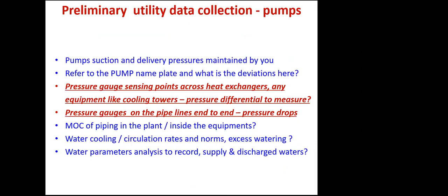I'm just giving a macro view of an industry trying to get ready for the energy audit. Each and every piece of equipment, right from the transformer, the motors, the production machines, the compressors, then the pumps. What are the pump suction and delivery pressures? The pump nameplate gives a lot of inputs. You store the nameplate or take its details and go with the pump manufacturer's OEM technical specifications. The nameplate gives the basic inputs, but the technical specifications tell you the operating temperature of the fluid and all the other inputs. What is the allowable delta P across the pump?